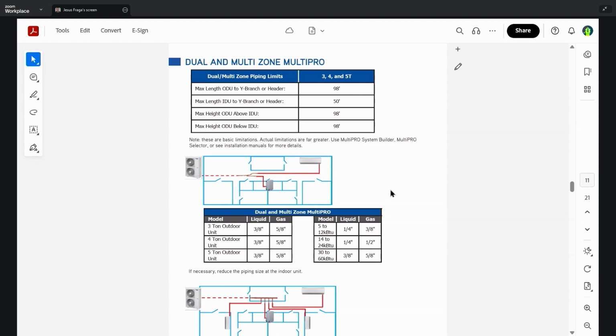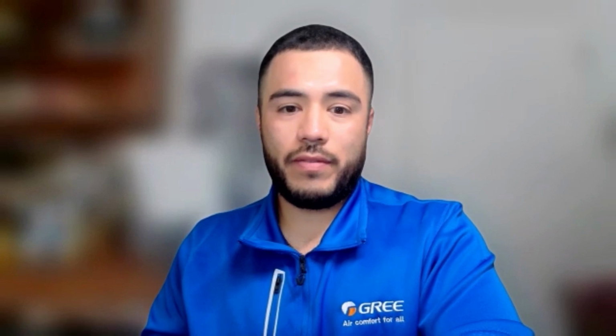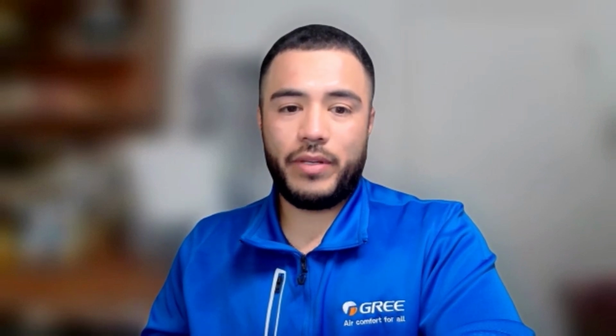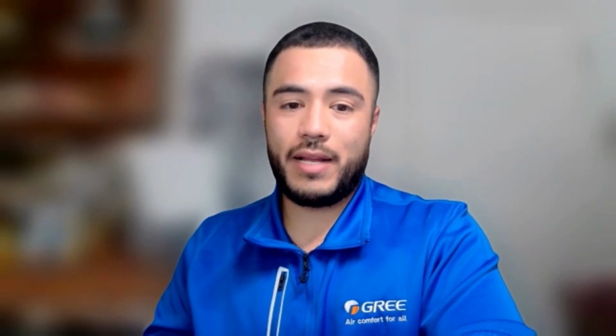That's what I always like to mention, that we actually have the software on our GREE commercial site. It's a VRF selector. You can actually download it. It's free. You punch in your outdoor units, your indoor units, and your copper links, and it'll actually tell you if it accepts the design and the additional refrigerant charge as necessary for your application.